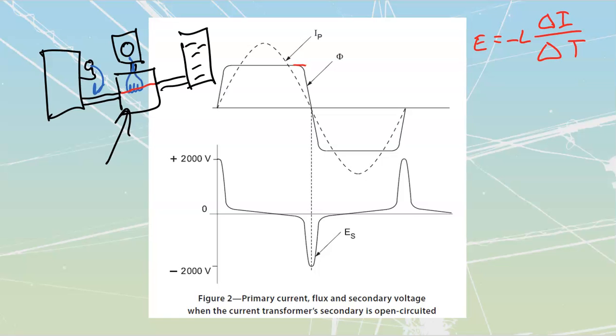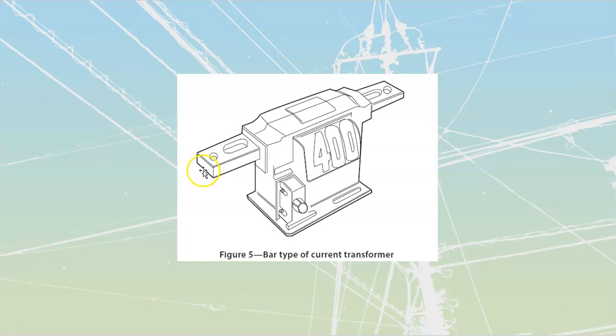These little shorting terminals should always be clear. You'll see them on something like this — I'm jumping a few pictures ahead here. It's a bar type current transformer, very common. Sometimes they look like this, with just a single bar in — we'll bolt our incoming lugs onto here and our outgoing lugs onto there. Other times it'll look like this, kind of double wide.